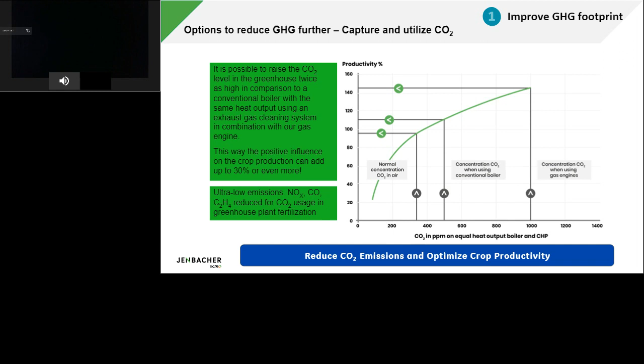As an example, 100 kilowatts of fuel input is more or less 341,000 BTUs. In a boiler with an efficiency of 95%, you can produce 95 kilowatts thermal and 18 kilograms of CO2.